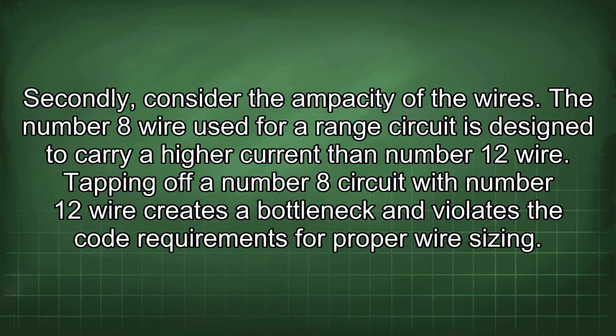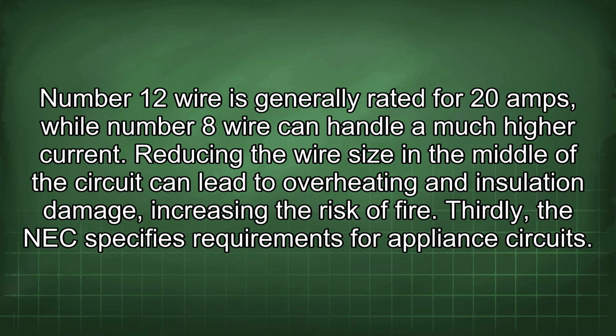The number 8 wire used for a range circuit is designed to carry a higher current than number 12 wire. Tapping off a number 8 circuit with number 12 wire creates a bottleneck and violates the code requirements for proper wire sizing. Number 12 wire is generally rated for 20 amps, while number 8 wire can handle a much higher current. Reducing the wire size in the middle of the circuit can lead to overheating and insulation damage, increasing the risk of fire. Thirdly, the NEC specifies requirements for appliance circuits.